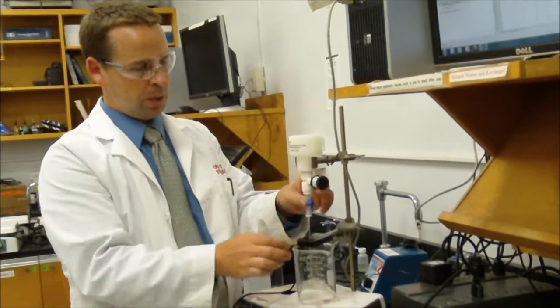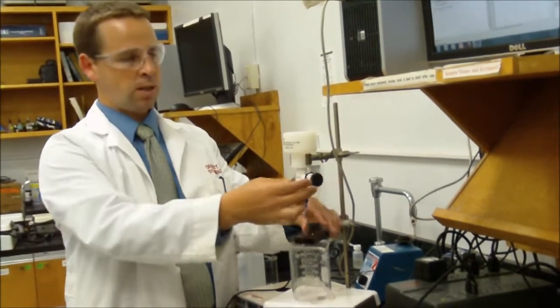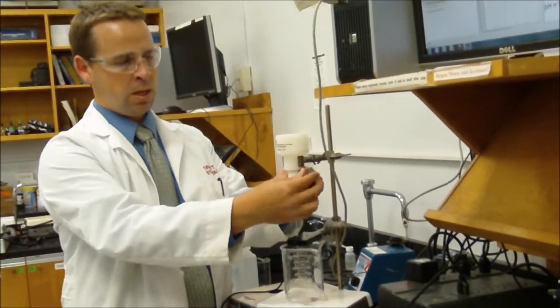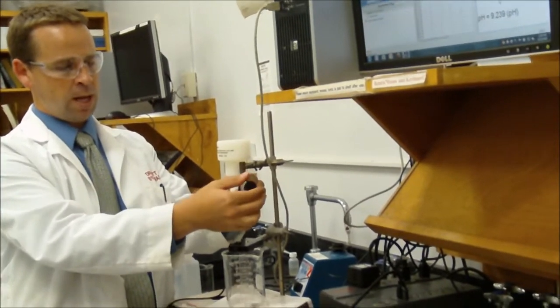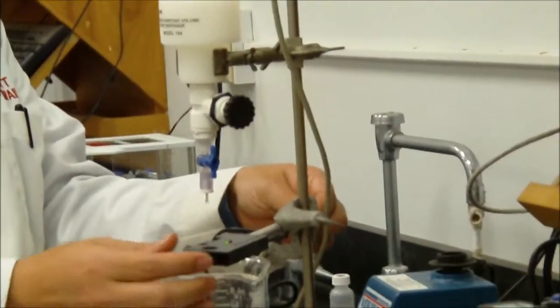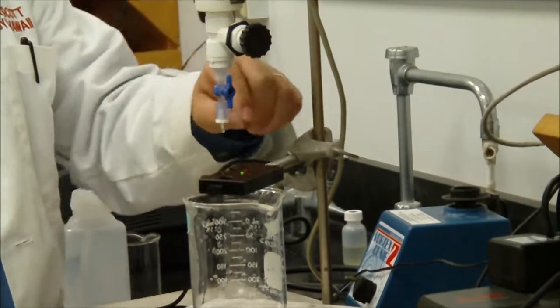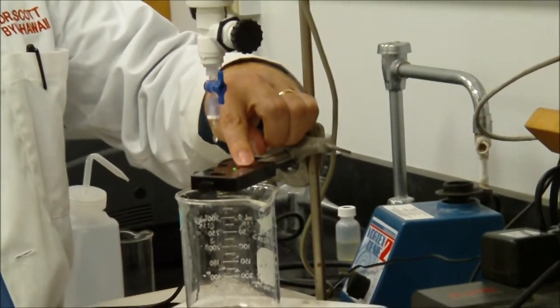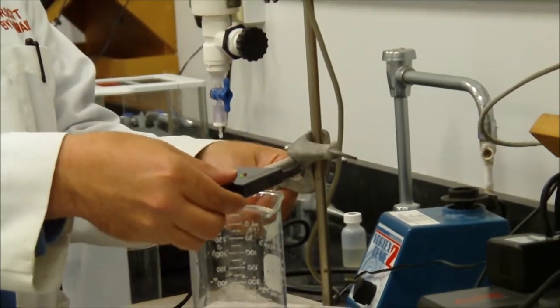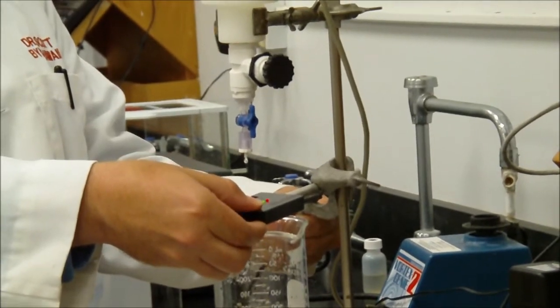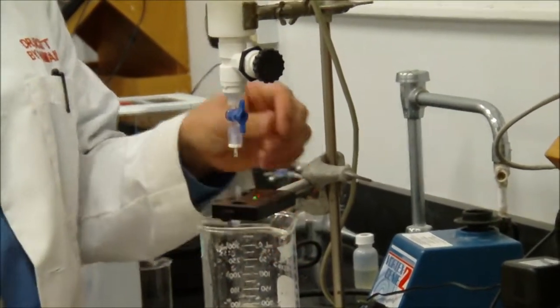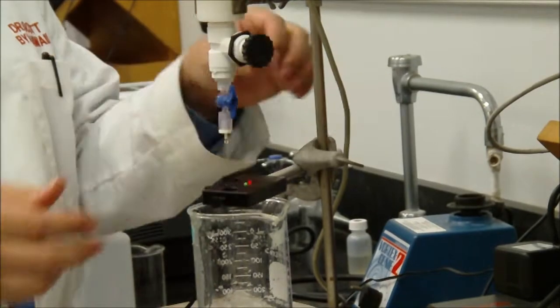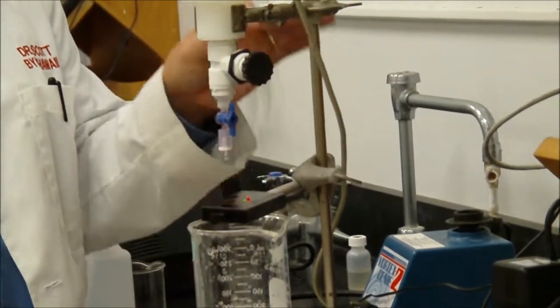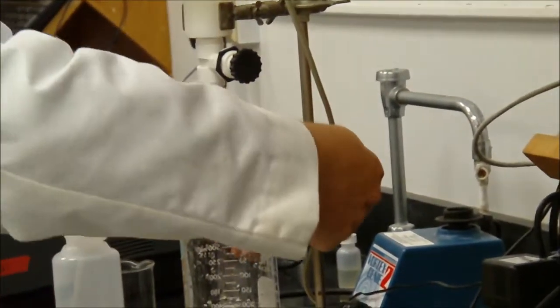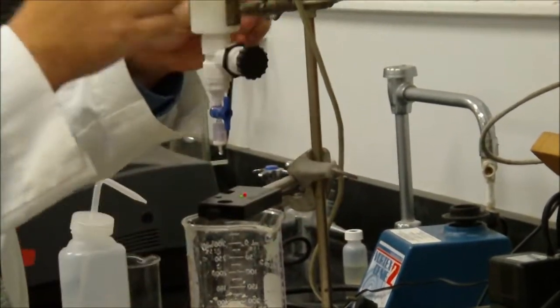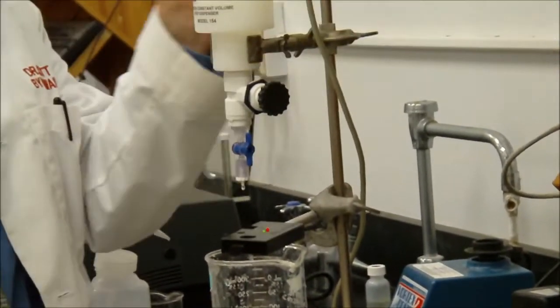So I open it up, and I see that it's going way too fast, right? So this controls my drop speed. So I righty-tighty, turn it to the right until the drop speed is what I'd like. It's right about in the right vicinity, but I can see the red light's not flashing, so I'm still not counting my drops. So it looks like I have to scoot this forward just a little bit until I can see that it's counting every drop. And I can slow that down a little bit more. All right, so now we're all lined up. I want to give these an extra tight turn so that nothing changes. All right, so everything's set.